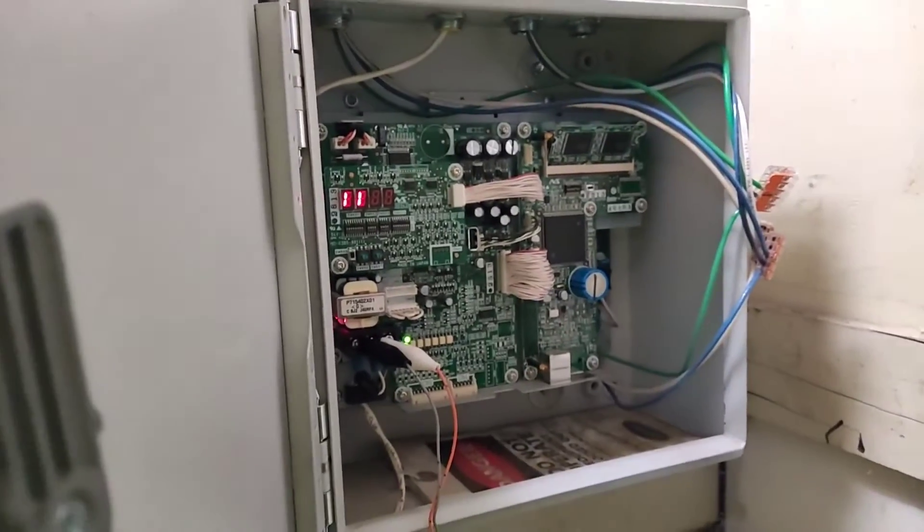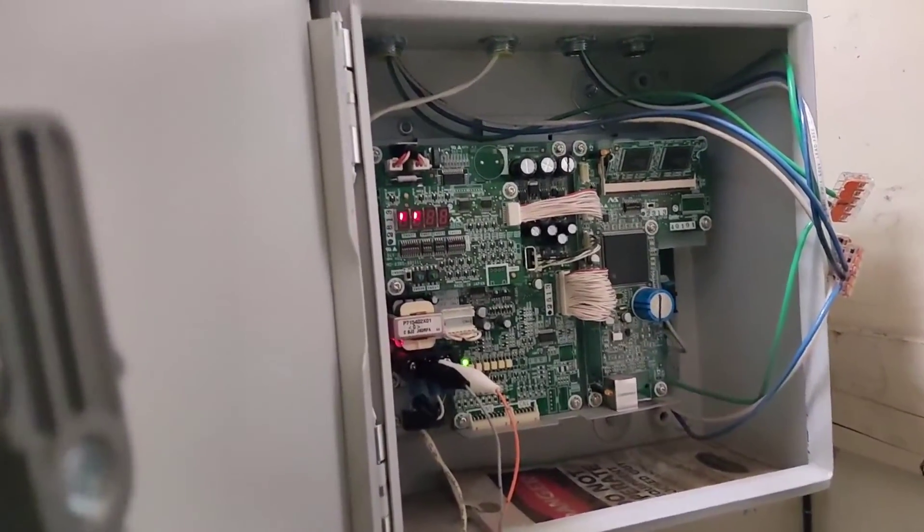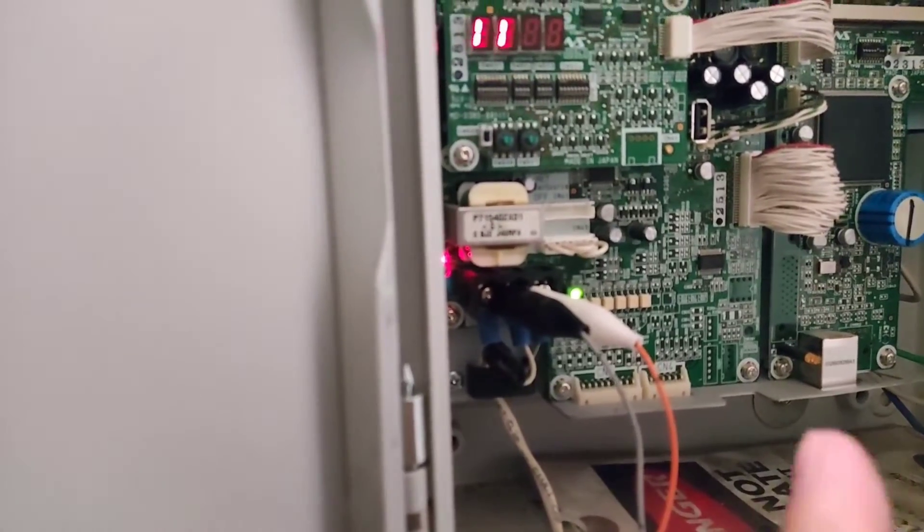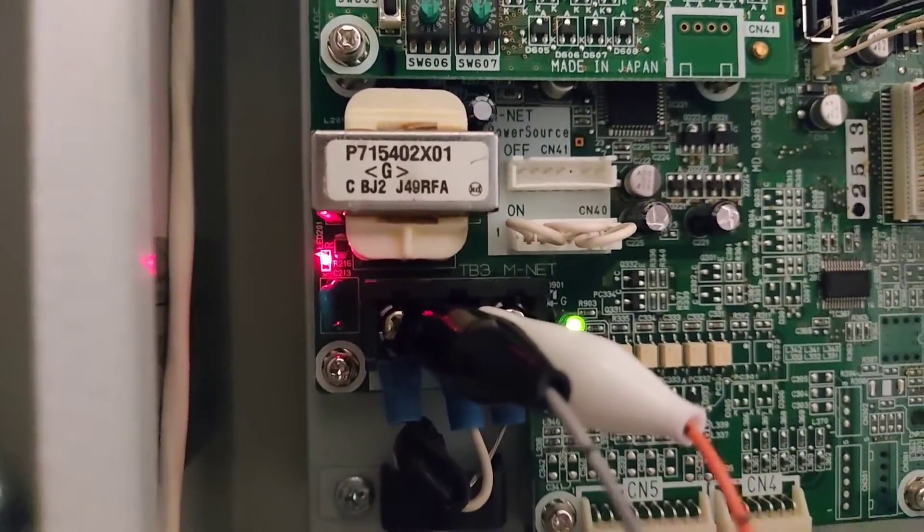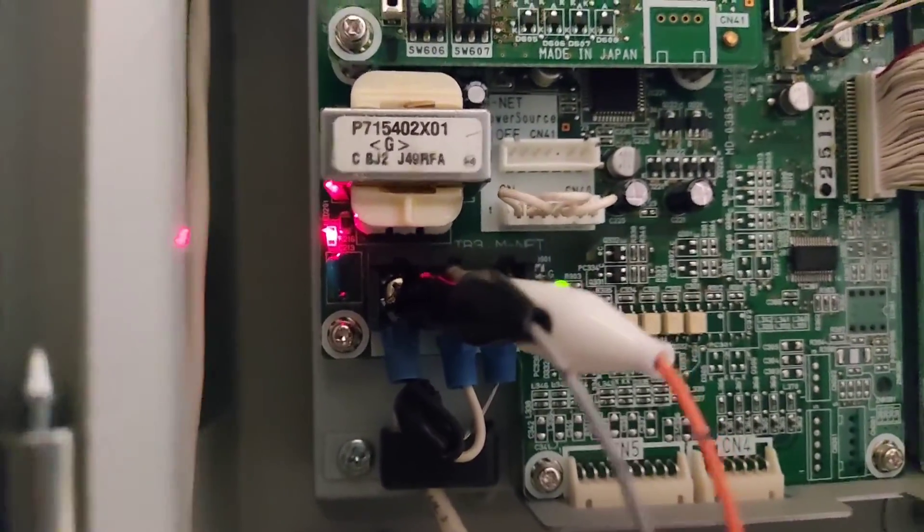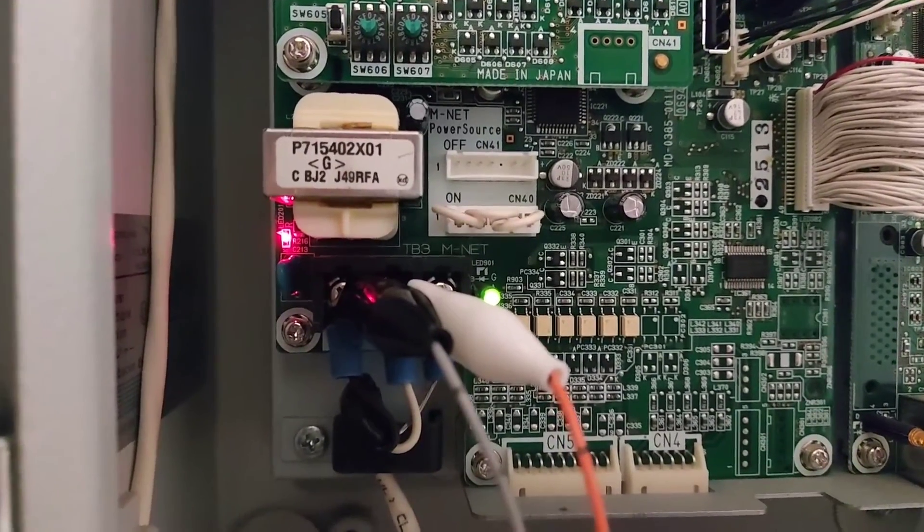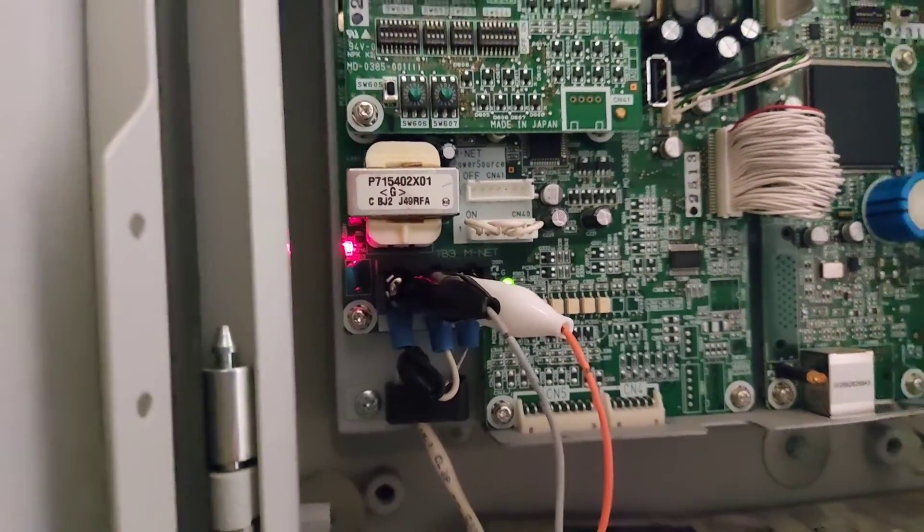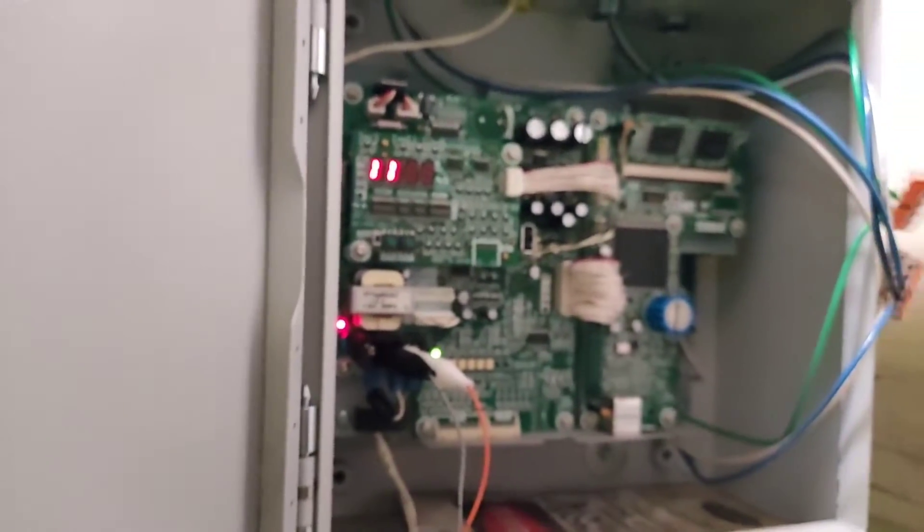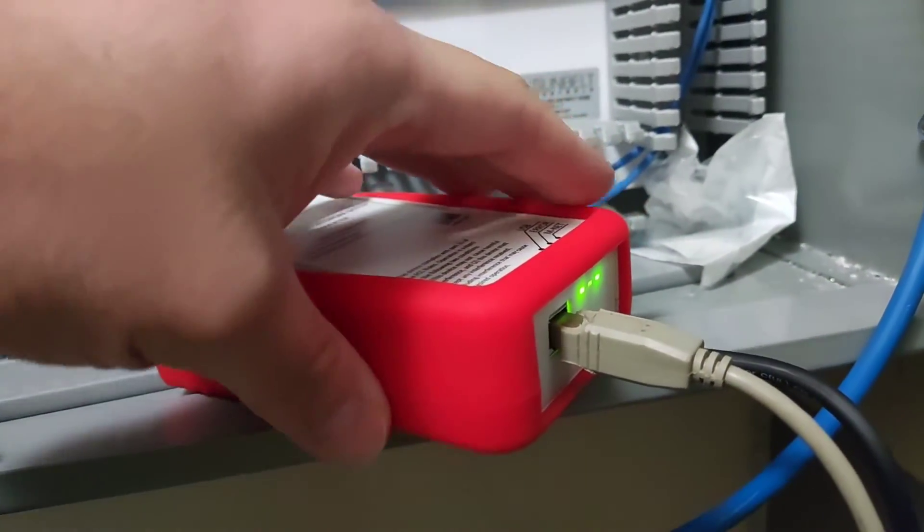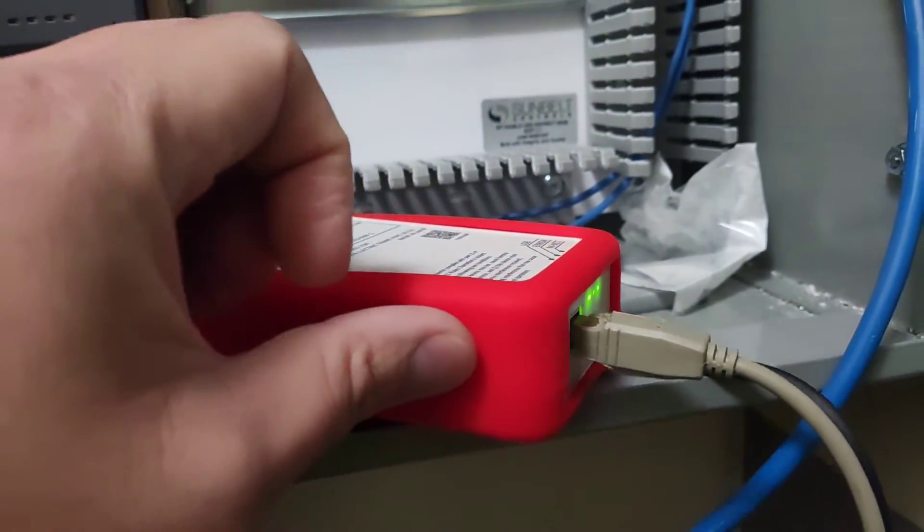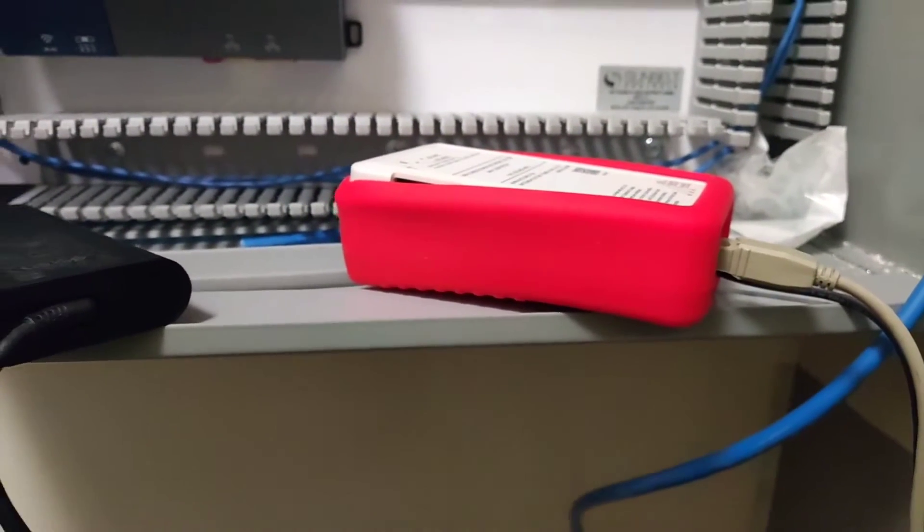When you open the cover, you'll see the M-Net connection right here. There will be two leads on the converter which you want to connect to the appropriate connection which you can see down below here. I'll post a picture of this so that it will be more clear. Make sure the controller is live and powered up. You'll connect the two leads and the USB. And it uses a USB-B connector which is your printer cable. And you'll plug that into your computer.